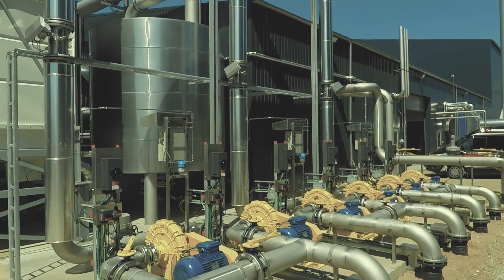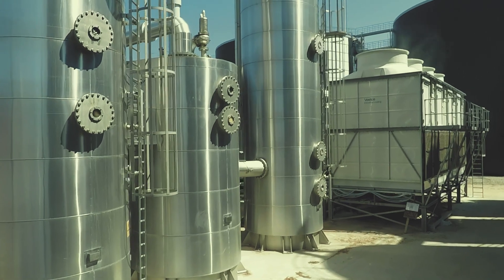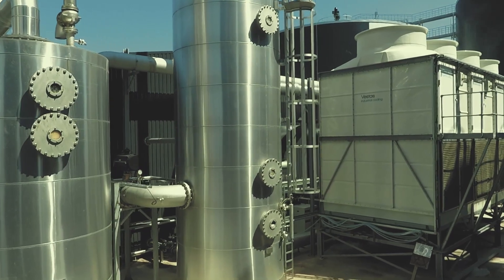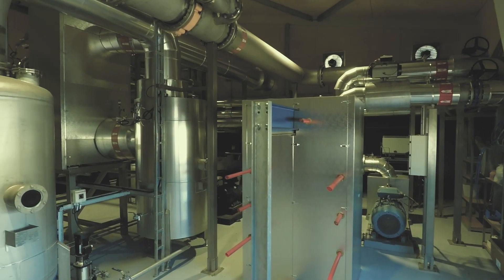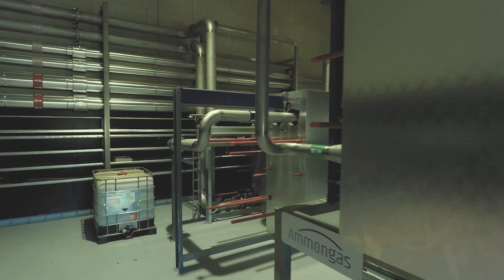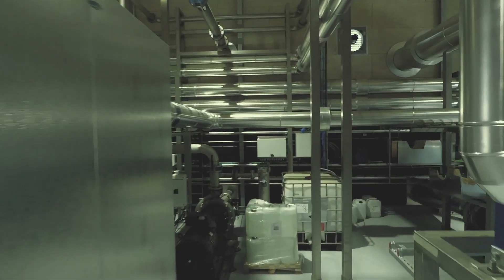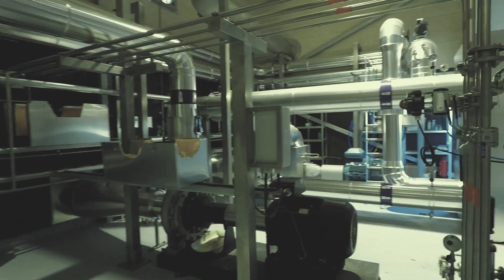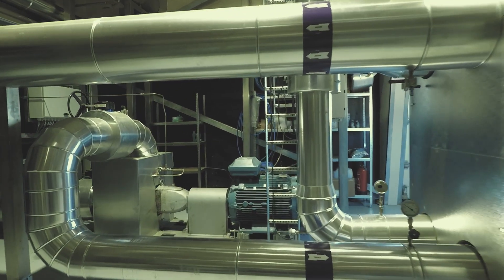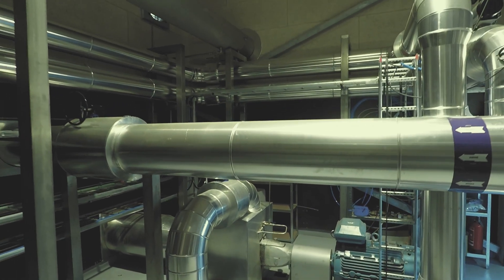Biogas is pumped out of the process tanks to the upgrading unit using six gas boosters. The upgrading system is an amine plant supplied by Ammongas. The upgrade unit is built to treat 7,500 cubic metres of biogas per hour, but additional capacity is expected. Following the upgrade process, the bio-methane is between 98 to nearly 100% CH4, which is fed to the compressor station.